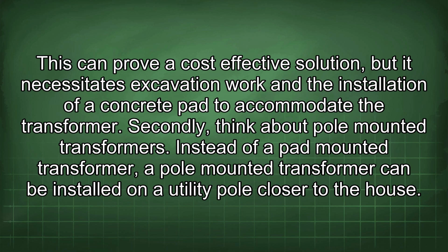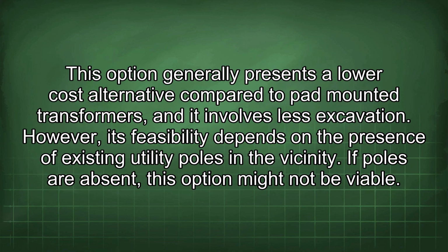Secondly, think about pole-mounted transformers. Instead of a pad-mounted transformer, a pole-mounted transformer can be installed on a utility pole closer to the house. This option generally presents a low-cost alternative compared to pad-mounted transformers, and it involves less excavation. However, its feasibility depends on the presence of existing utility poles in the vicinity. If poles are absent, this option might not be viable.